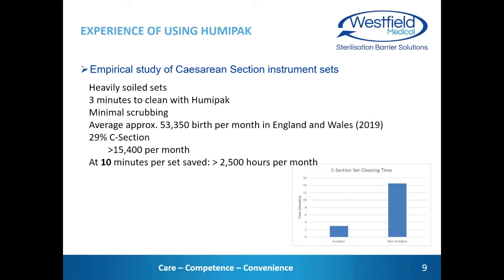Although the primary purpose of HUMIPAK is infection control through improved decontamination, we can't ignore the costs associated with using the product. So we carried out a study in conjunction with a UK sterile services department where HUMIPAK is used, particularly for caesarean section sets. The feeling from the unit was that HUMIPAK saved them time when they were used for these heavily soiled sets. So we looked to verify this by carrying out back-to-back studies with and without HUMIPAK. With HUMIPAK, the sets took around 3 minutes to clean, compared with 14.5 minutes without HUMIPAK. So I'm sure you'll agree this is a significant difference.